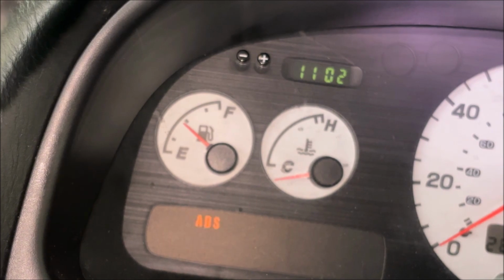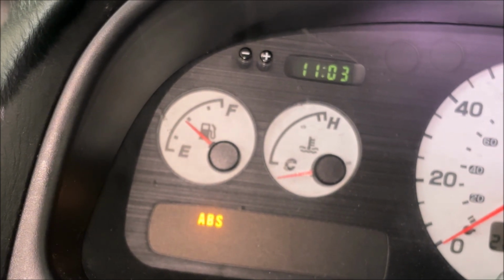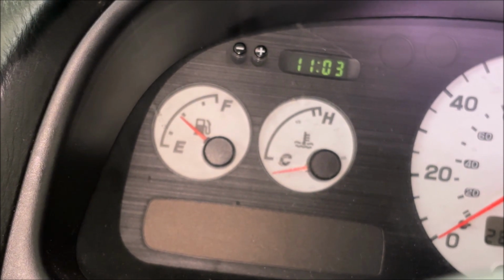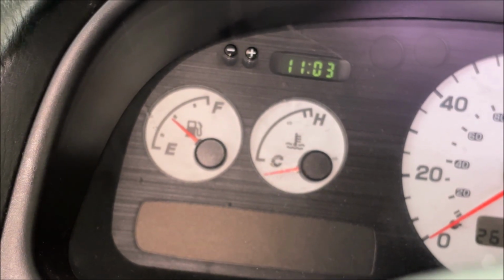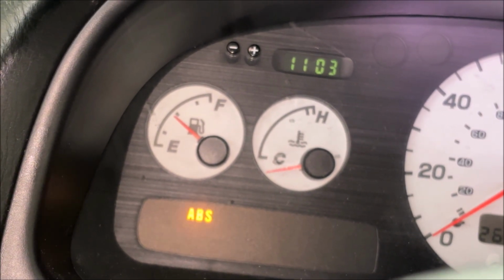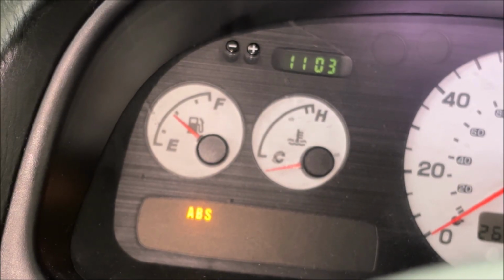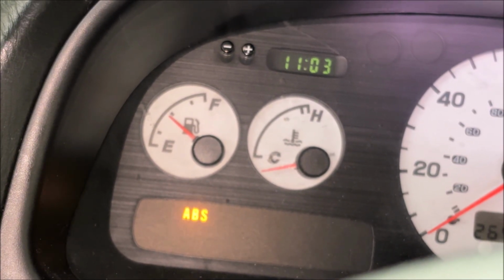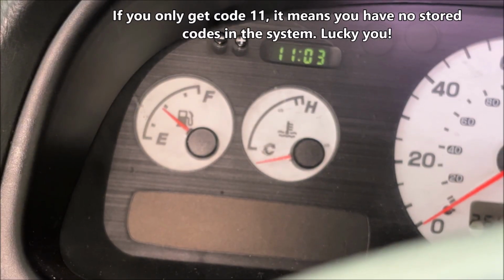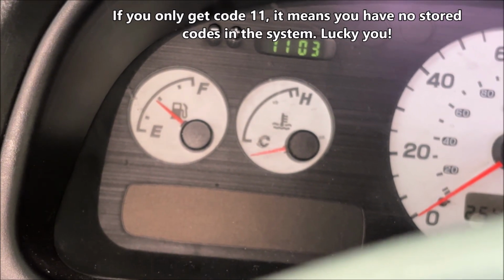So I've got one long pulse and one short pulse, so that's 11, and that means you're starting the sequence - that's like a blank. Then I've got 3 long ones and a 1, so that's 30 plus 1, so that's code 31. Then it goes back to 11, which tells me there are no other codes. So the only code stored is code 31, and I have to go figure out what that means.